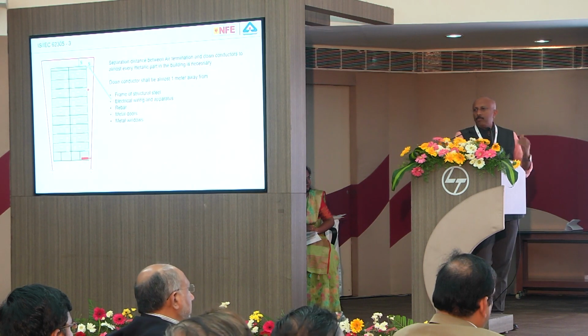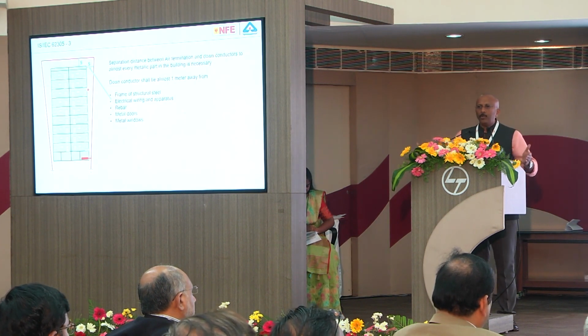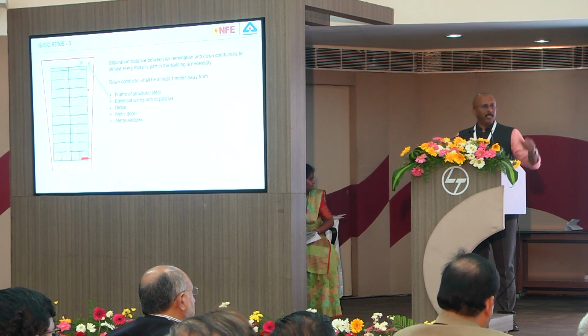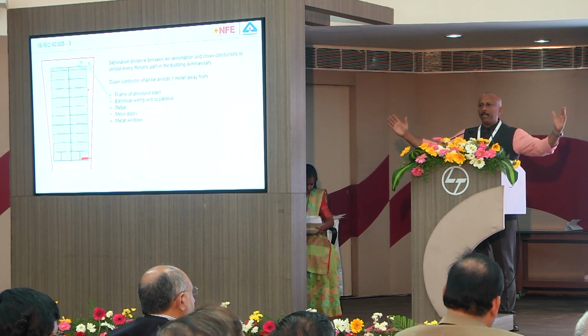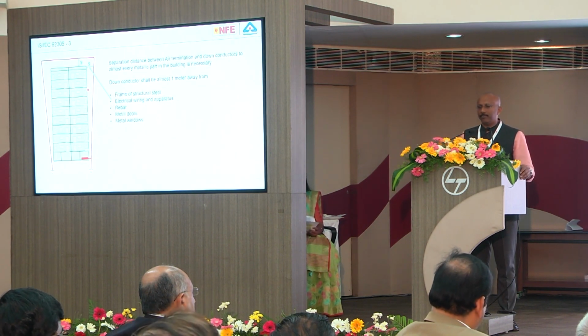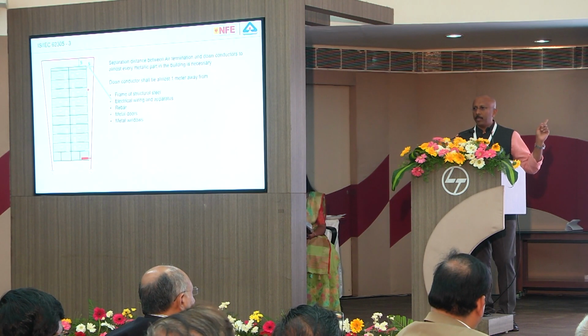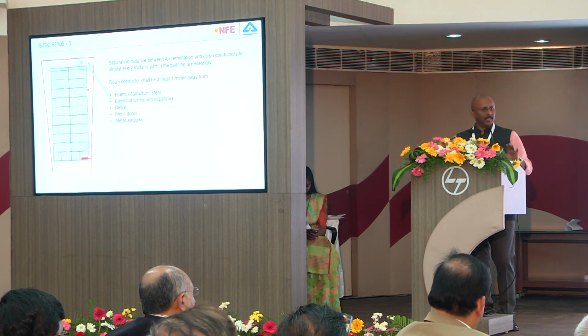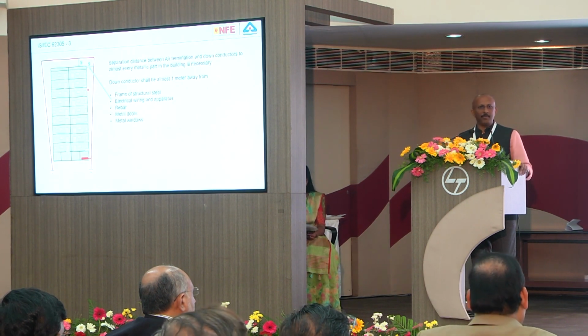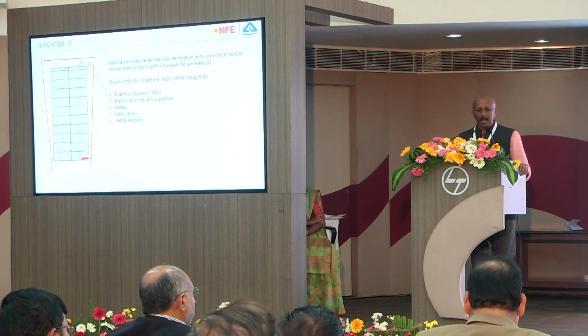Now a building which is very well protected with separation distance will look like this. You have a building, the air termination has to be gradually away from the building. At the top, you have to keep the separation distance. Example, the calculation says 1 meter, means your air termination grid and the down conductor at the top has to be 1 meter physically away from the building. Is it possible to make a lightning protection half meter away from the building? Technically not possible. This also means that in high-rise buildings, if we make a lightning protection without calculating the separation distance, again it is to show the authority. Practically, once there is a lightning strike, the result you know very well. Now, you need a separation distance from frame of structural steel, electrical wiring, rebar, metal doors, metal windows.